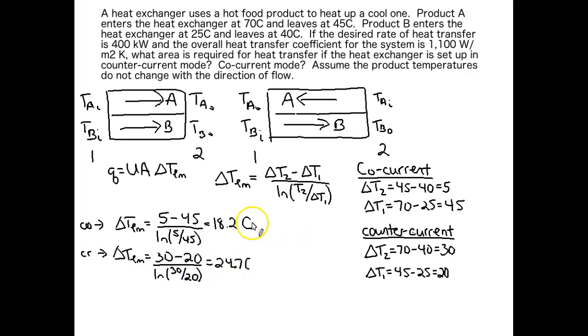Let's calculate that delta T log mean for both our co-current and our counter current types. Okay, we can see that for co-current, we have a smaller log mean temperature difference than for counter current. And if we want to transfer the same amount of heat, we're going to need different area for each one. So let's work out what that area is equal.